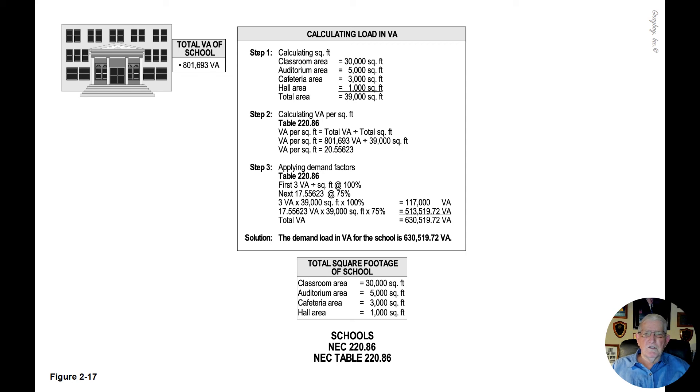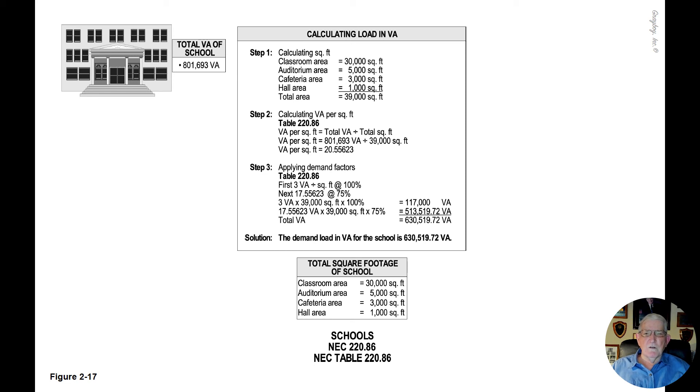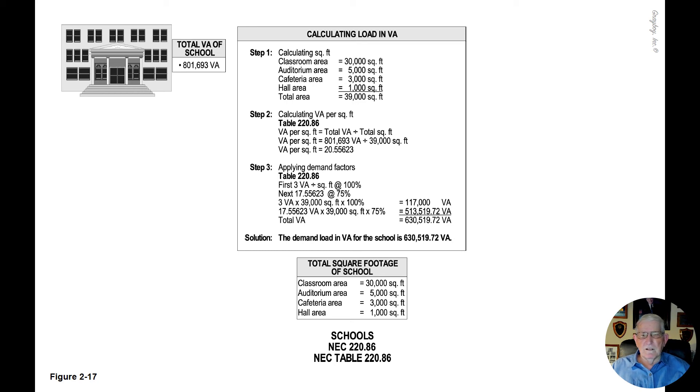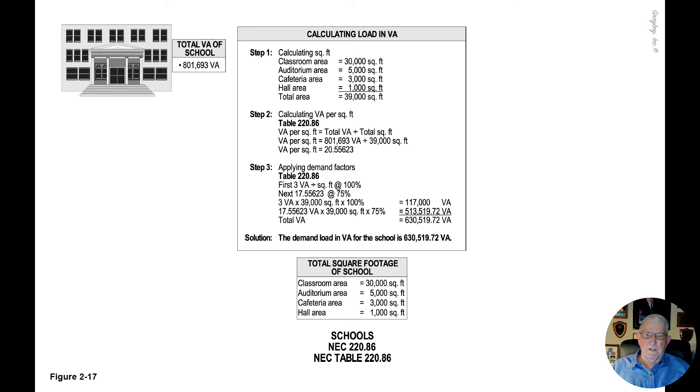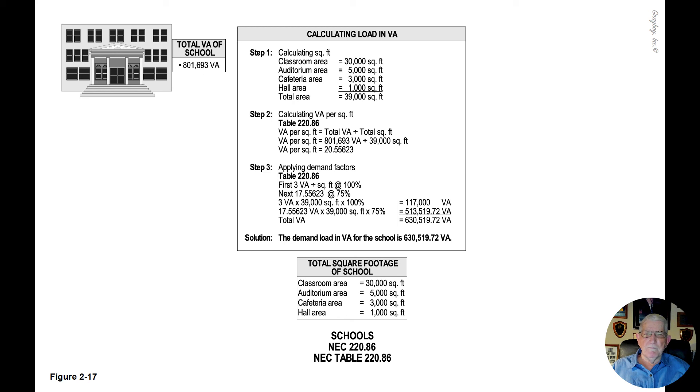Step three is the application of the demand factors. The first three VA per square foot at 100%, the next 17.55623 at 75%. So when you take the 20.55623 minus the three VA, you come up with the next 17.55623 at 75%.